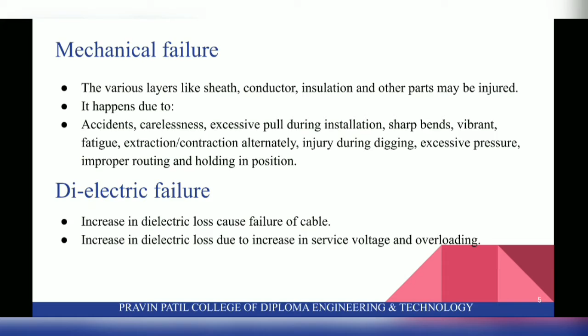Next is dielectric failure. Increase in dielectric loss causes failure of cable. Increase in dielectric loss is due to increase in service voltage and overloading. Next is thermal failure. Insulation degrades due to increase in temperature. Unequal temperature rises occur due to installation, construction and surroundings. Next is overloading. Next reason is that insulation in a hot spot gets ionized, with void formation, partial discharge and leakage current. So these are the reasons of thermal failure.